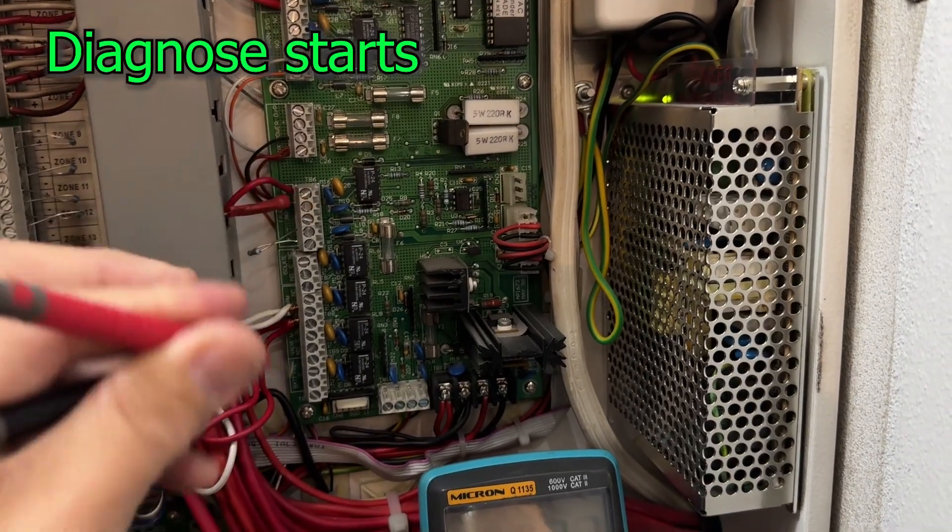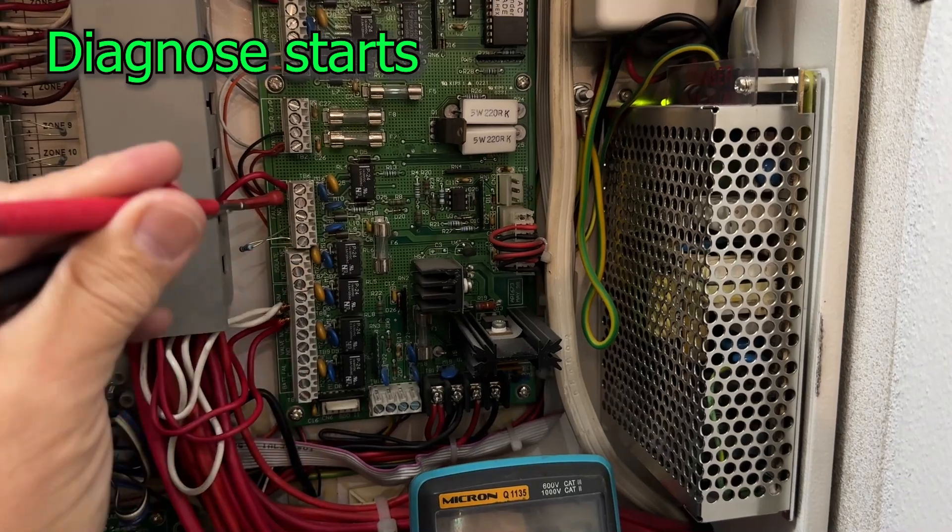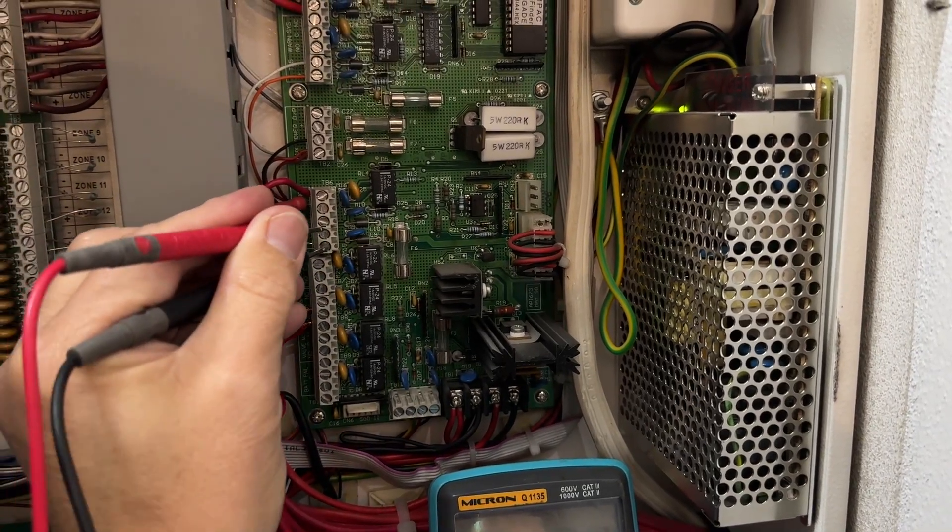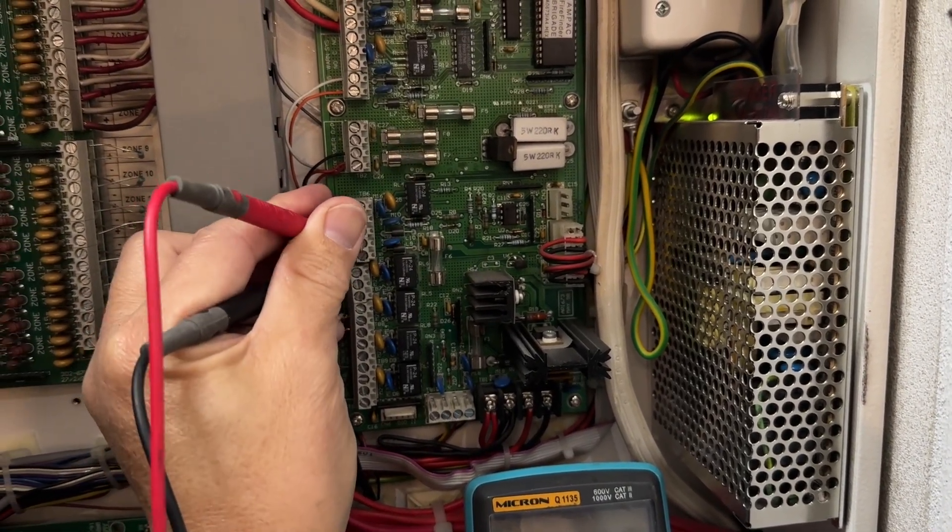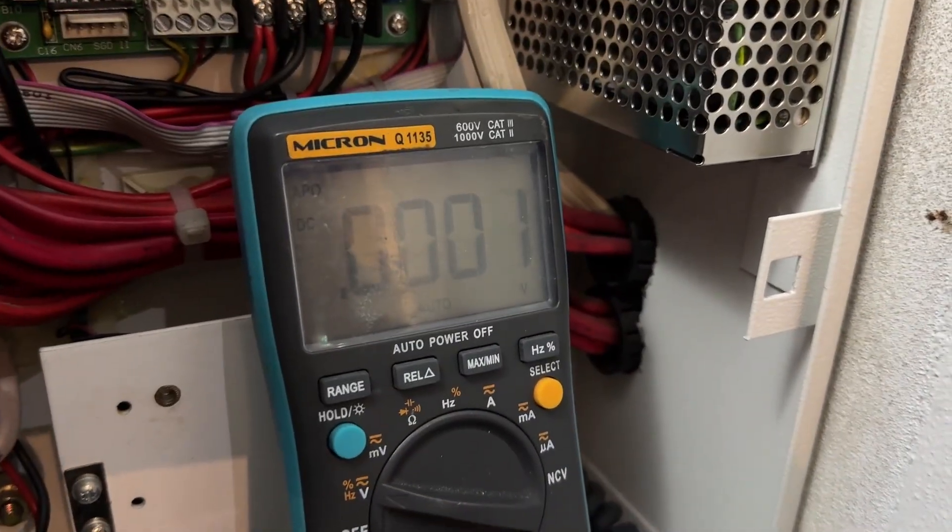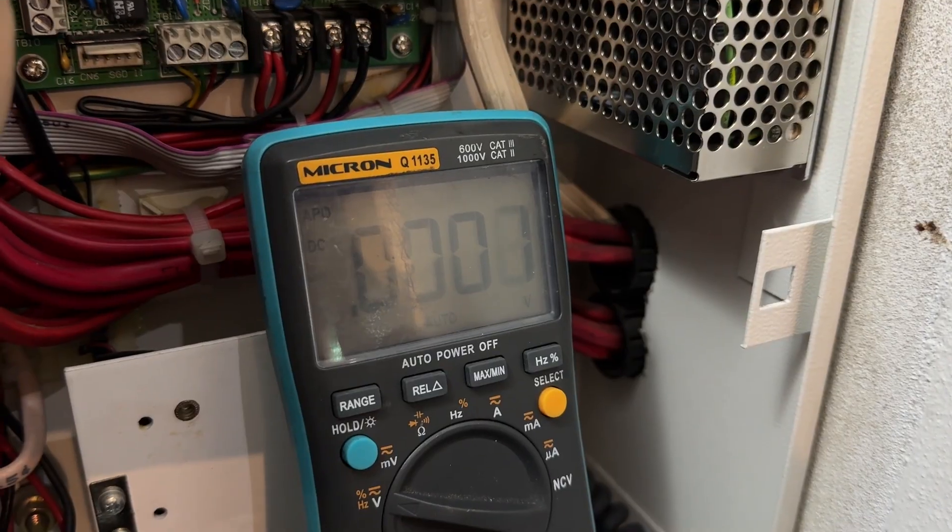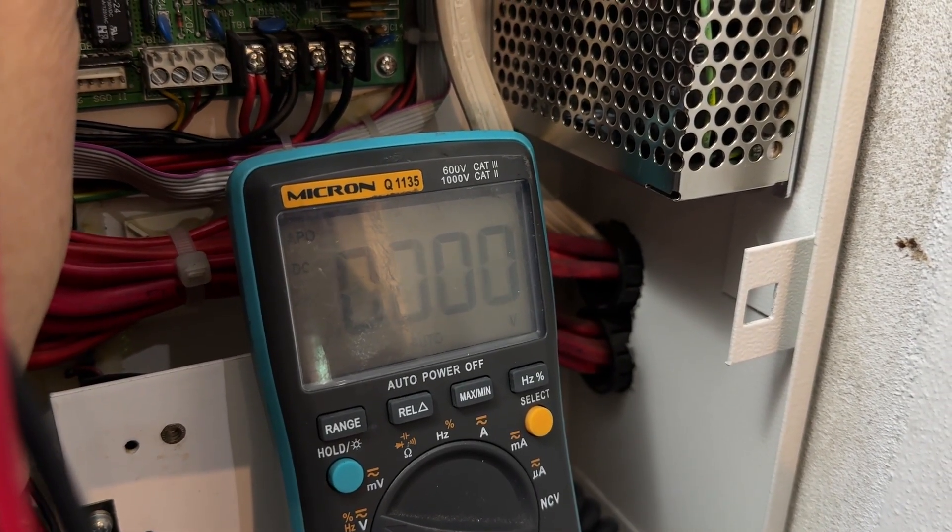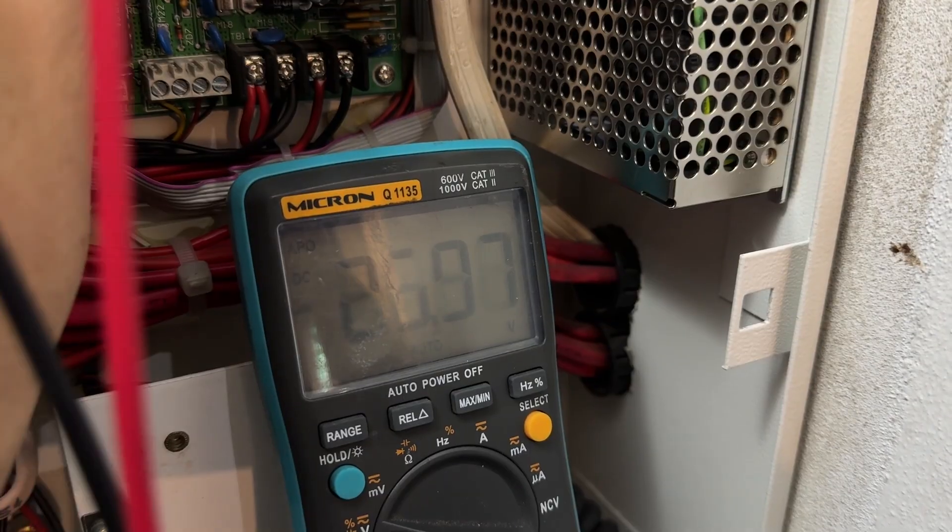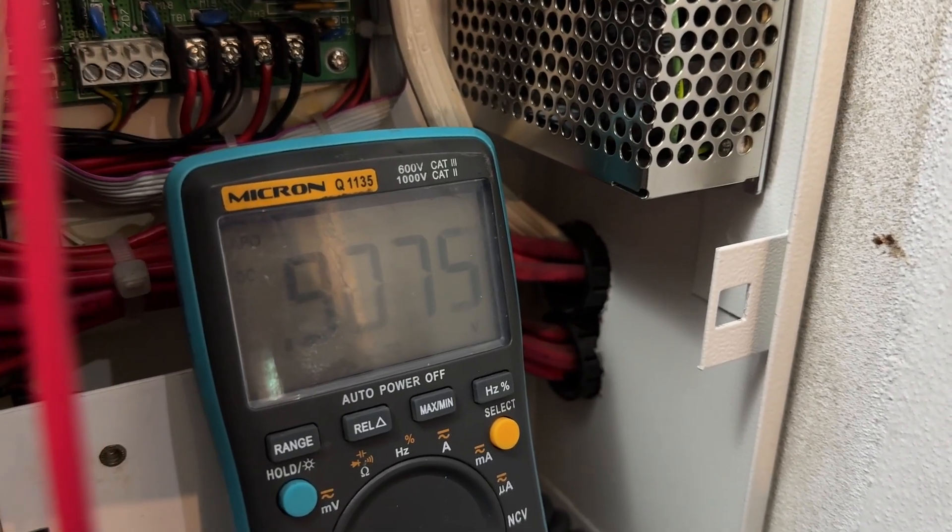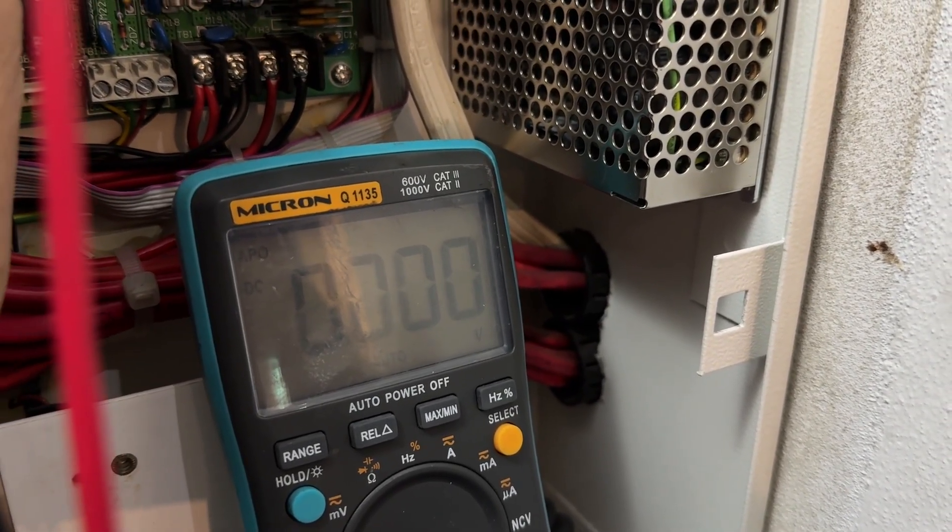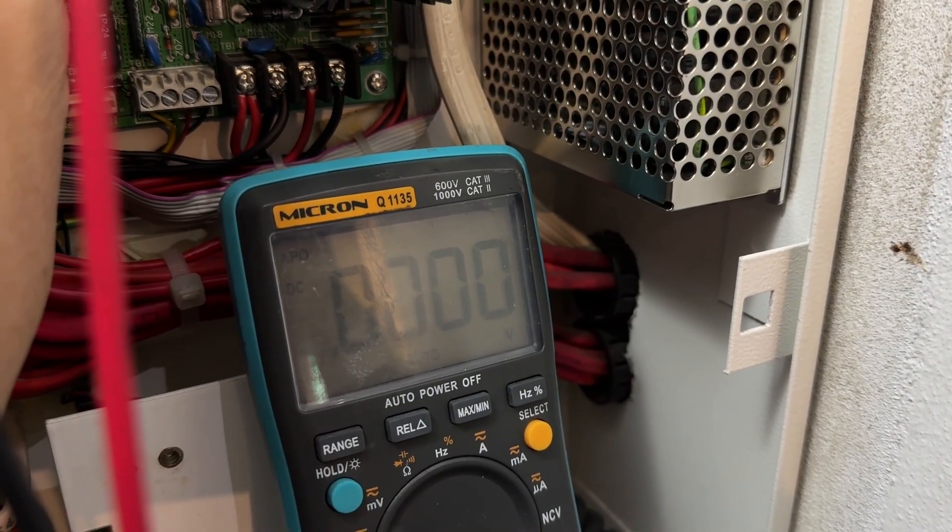So that is the fault relay with the resistor. I will put my multimeter on it. And my reading is zero and then it will, sorry, 25, then zero, then 25 again, and then zero. Okay, so that's where your fault coming from.